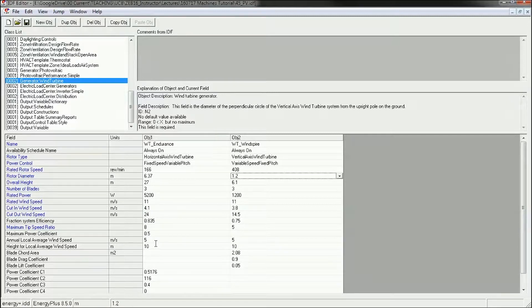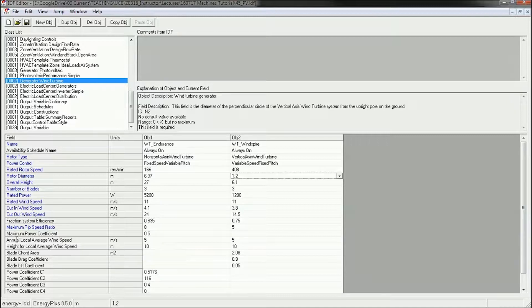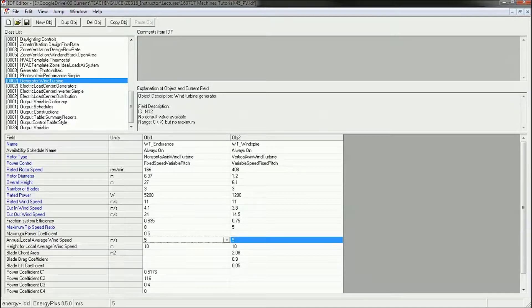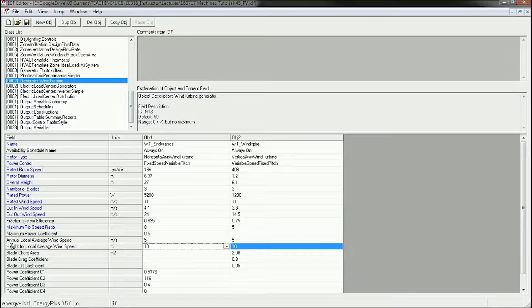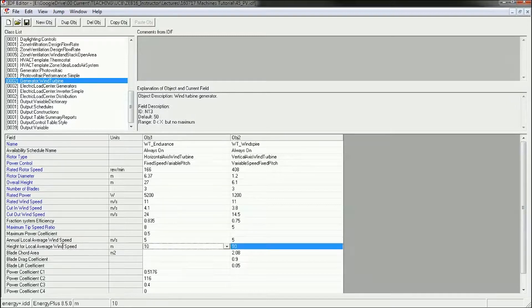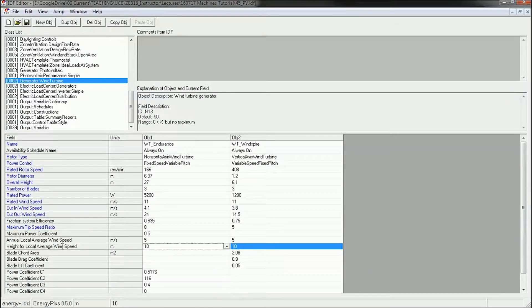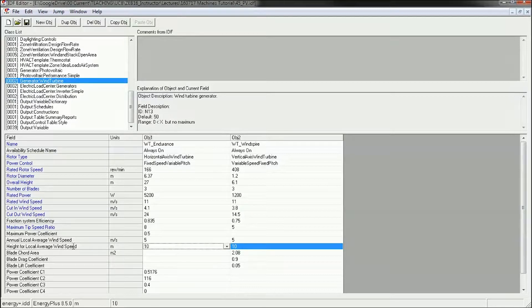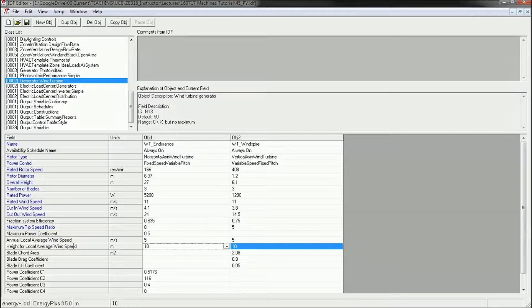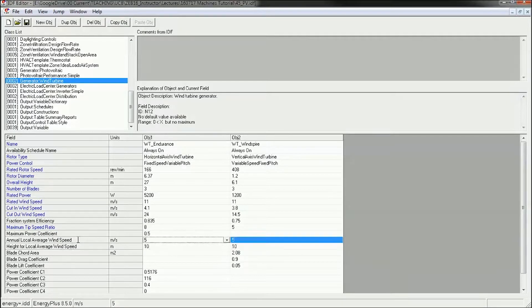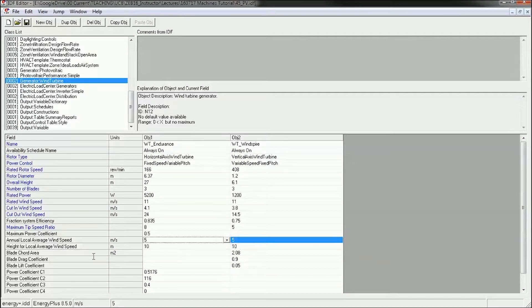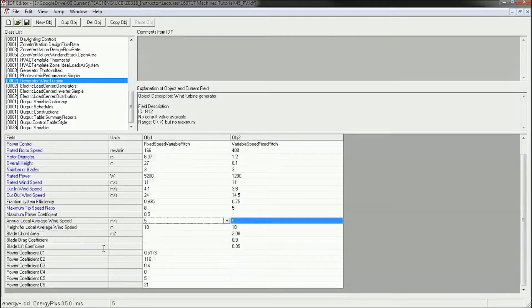The only thing that you might want to consider changing is the annual local average wind speed and the height for the local average wind speed. So these two help Energy Plus derive a more accurate understanding of wind speed throughout the year. It uses this as a coefficient to the climate data that it's reading. So it takes the wind speed from the climate data and then modifies that based on both the annual local average wind speed and the height for the local wind speed.